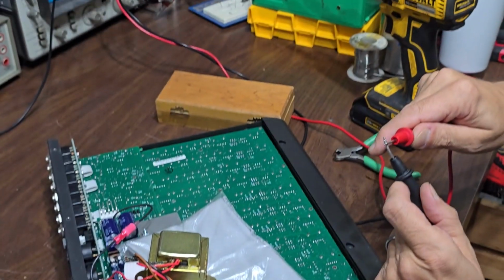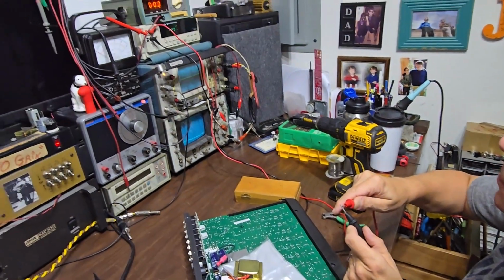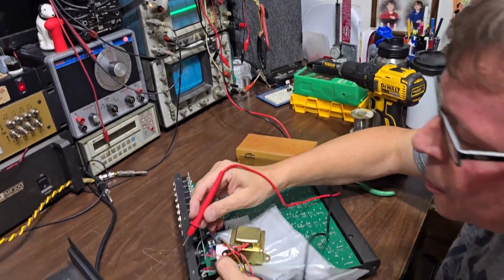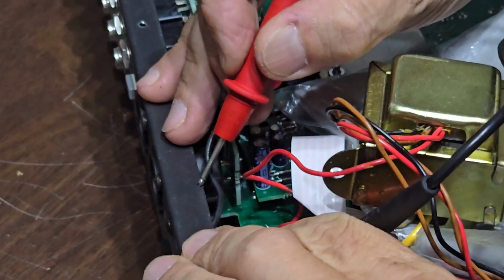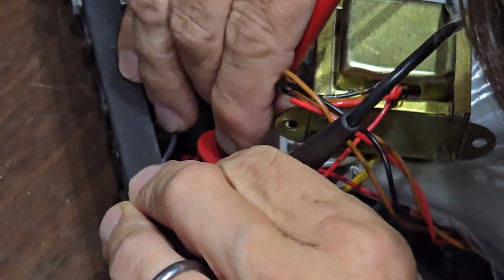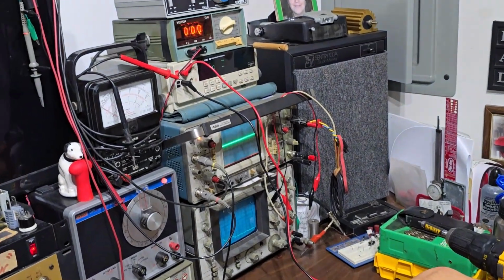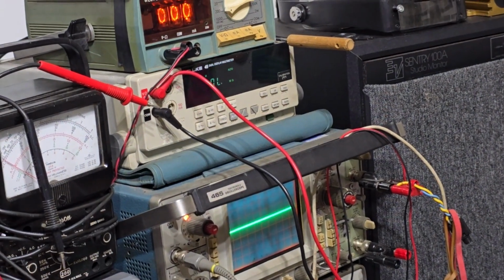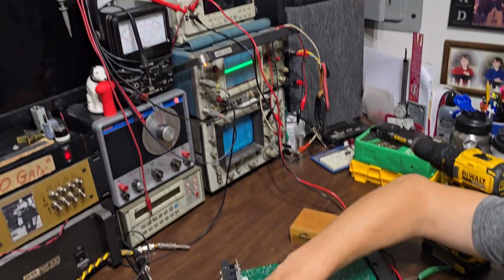So I'm going to check my zero, like I'm an old guy or something. I've got 0. Now I know that my meter's measuring 0. I know that I'm on the primary. And as you can see on the meter, it's open. That transformer's bad. I got to find a replacement for it.